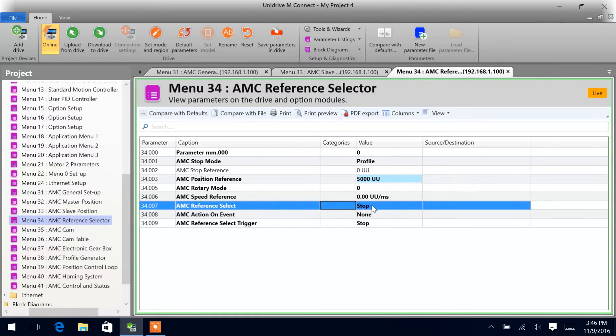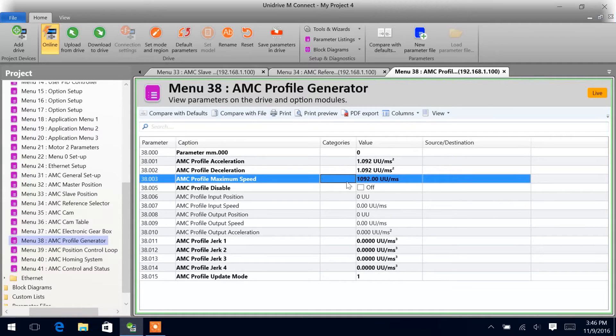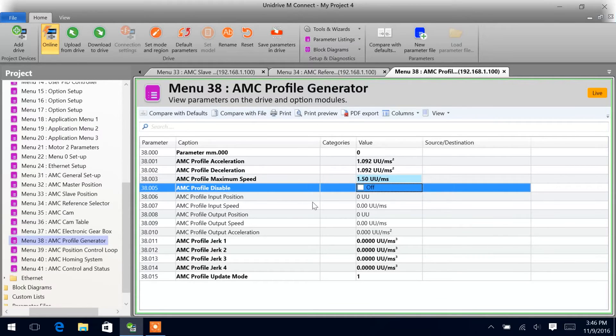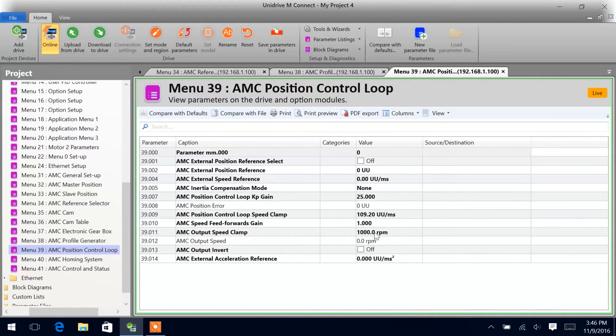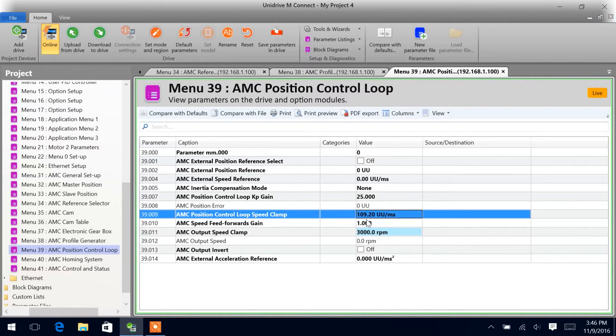Do not go ahead and select position relative yet — it will not take effect when you give it the run. You want to make sure that you do that after you give the run command. Coming to menu 38, which is our AMC profile generator — this is where our speed limit comes from. We'll change this to 1.5 and leave the acceleration cell as is. Next, coming into menu 39, this is our clamp area. We want to make sure that we set the motor clamp to 3000, ensuring this is above our AMC profile speed in menu 38, parameter 38003.